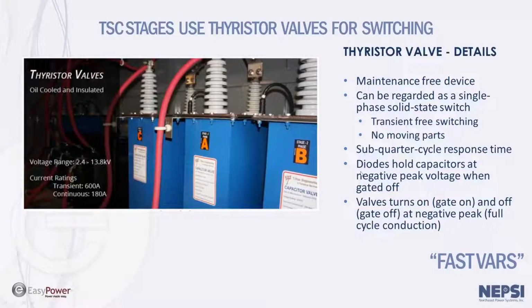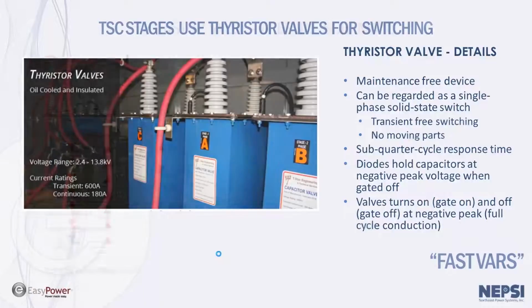It has a sub-quarter cycle response time, but when you consider control time and sensing time, typically we're on the order of about 1.1 cycles for the slowest phase to turn on. And if something like this were to break, it's basically a replaceable item. We send it back to the factory for repair, and we send a new one. This is a maintenance-free item. It turns on, transient free, turns off, transient free, and does not produce any harmonics.